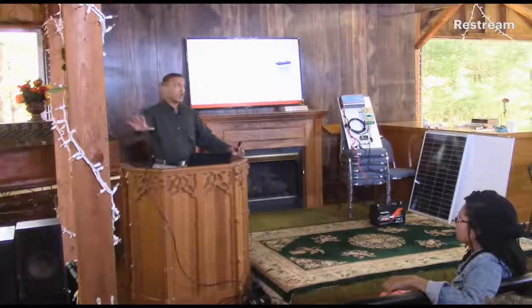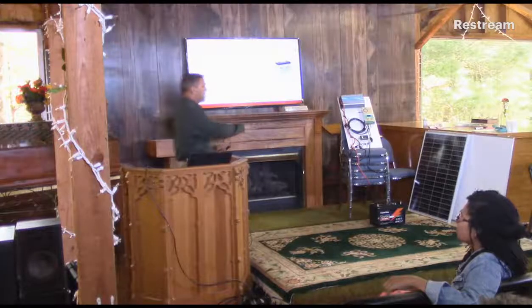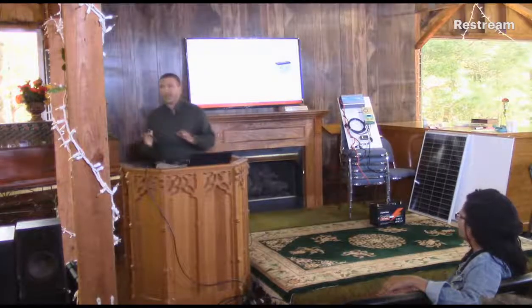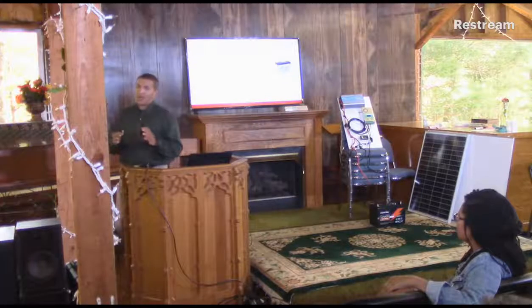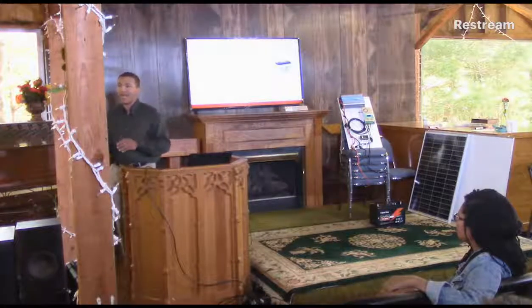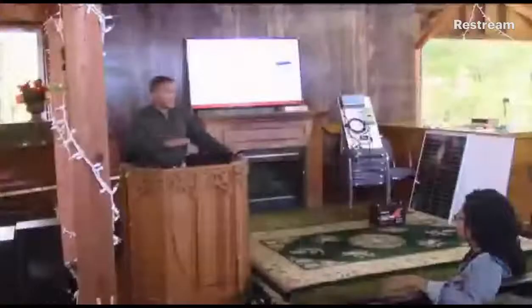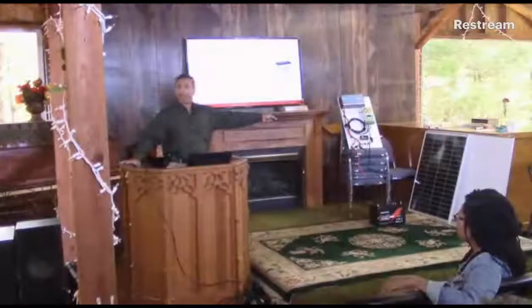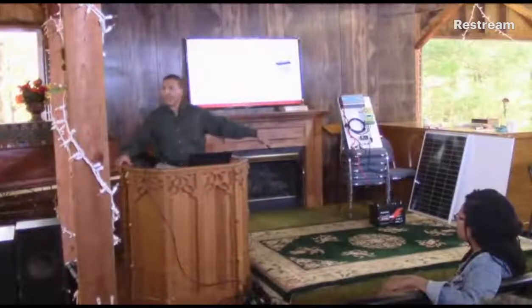Now, when you're running these things, you want to design your system so your batteries charge in about 4 to 4.5 hours based on the winter. If your system charges there, then your battery is good, and all the other power you're using comes straight from the panels, not touching the battery.